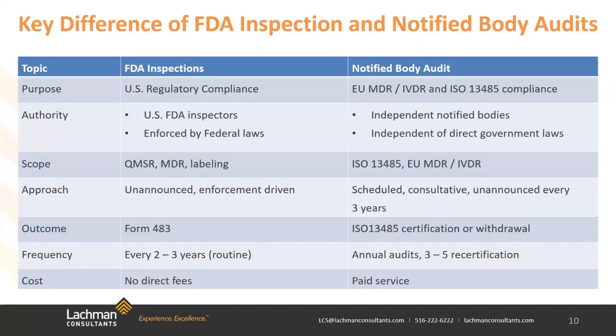So now that David has gone through from a high level perspective some of the key differences between FDA inspection and notified body audits, here's just a comparison of FDA inspection and notified body audits, highlighting some key differences in purpose, approach, focus, and some potential outcomes.